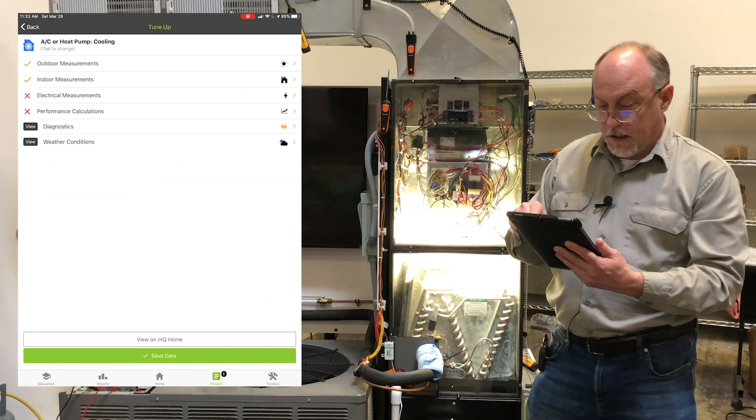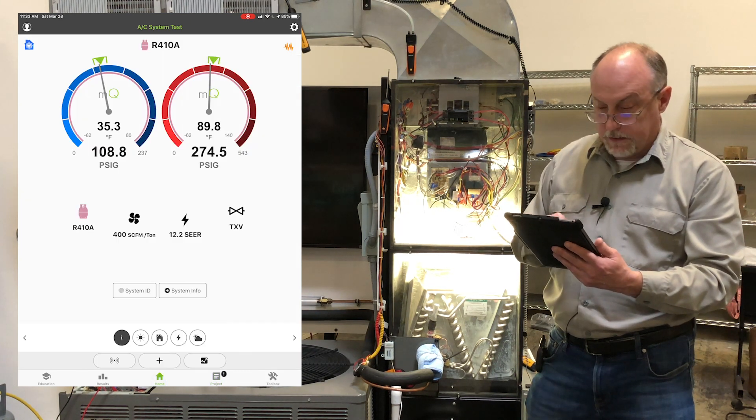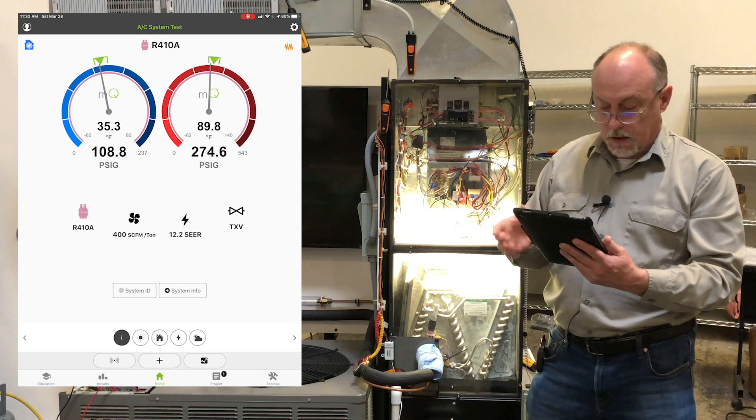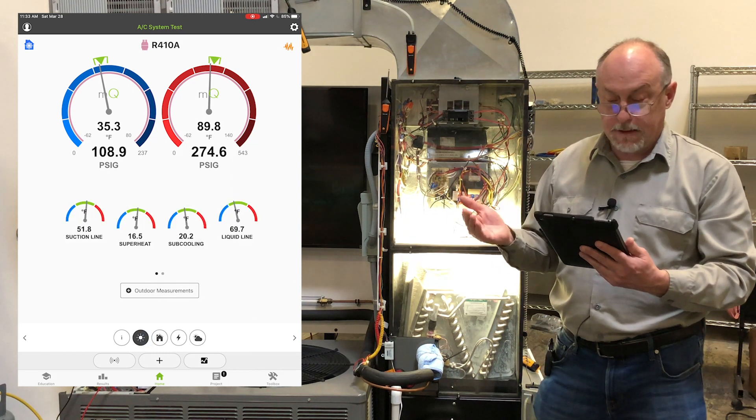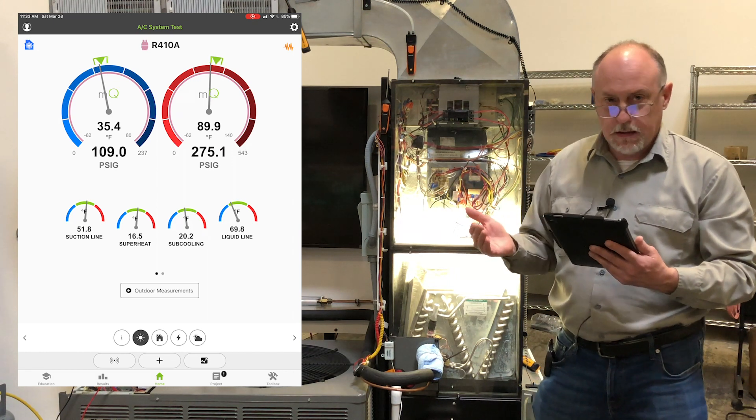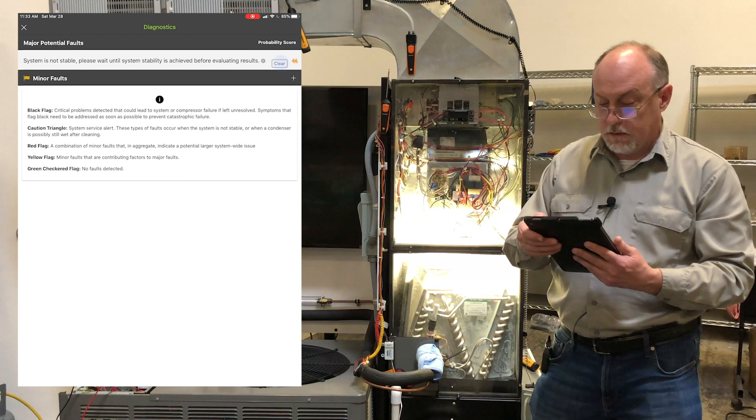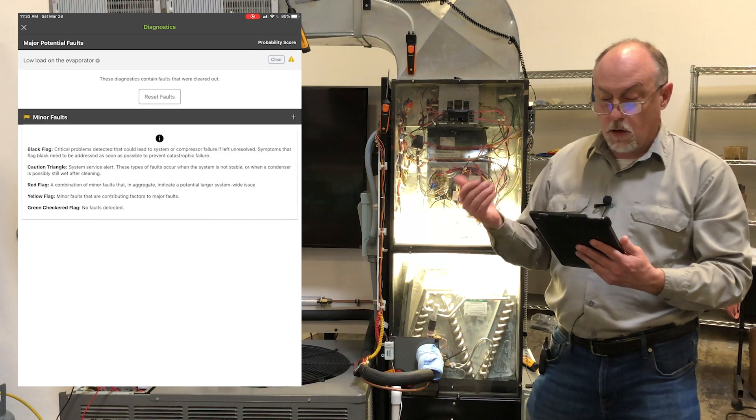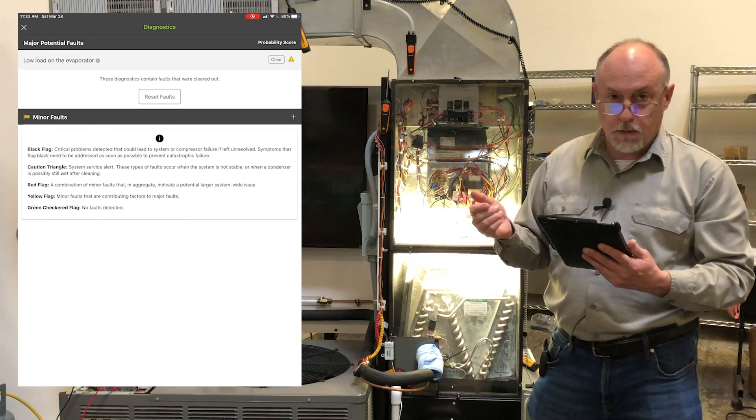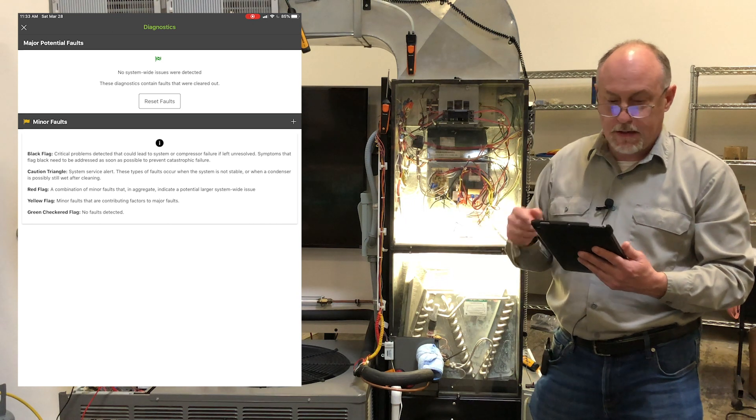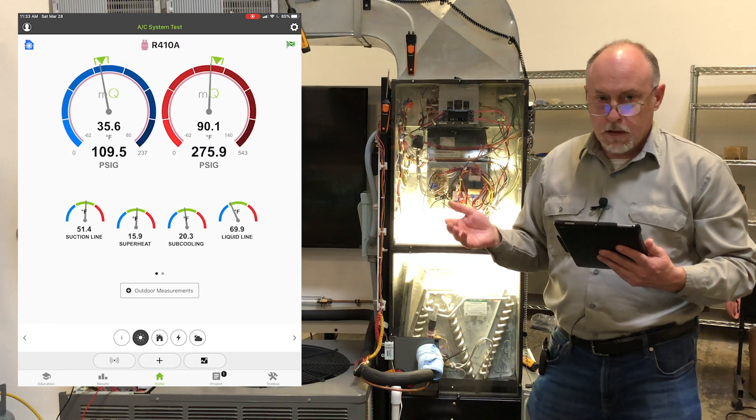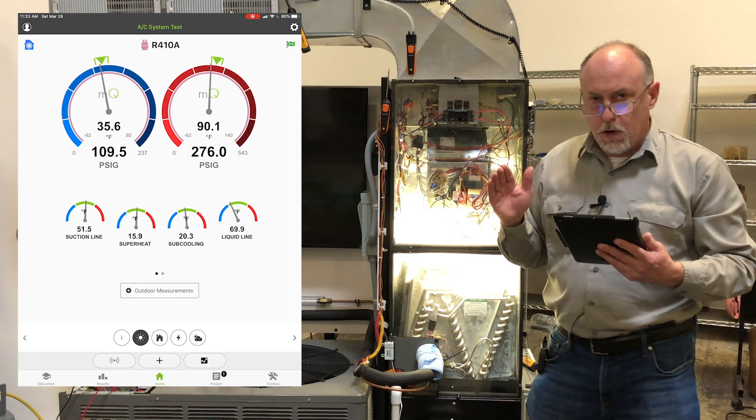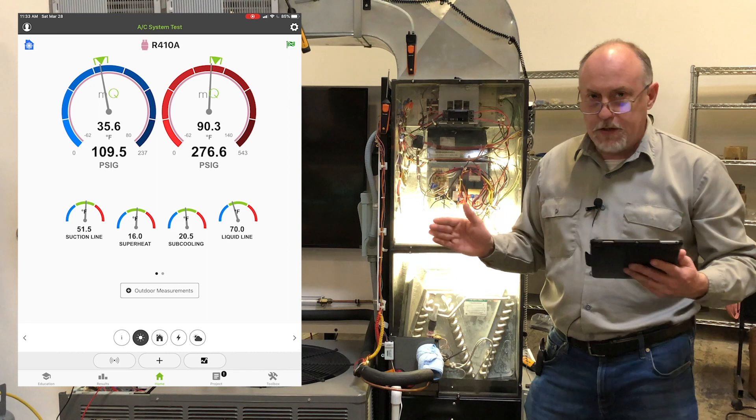And now when I go in to take the measurements, all I have to do is capture my electrical again. But let me show you what's going on. So now my targets, all my targets are right within the ranges that I would expect to see. So this allows us to very accurately troubleshoot the system. We'll just clear this out, I'll just hit clear on the stability here. We have low load on the evaporator. And that's about the only fault that we have. We cleared that low load fault out, you'll see there's no system wide issues detected. That low load is just sort of a notification.